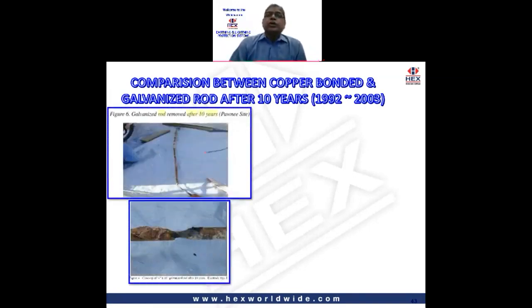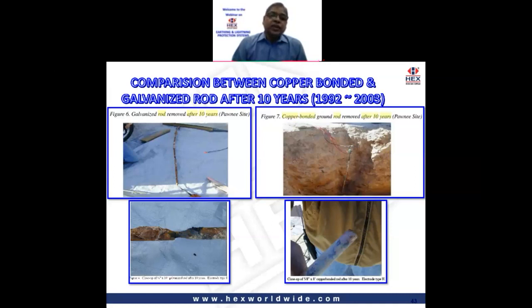So let us see, many people ask us this question: which surface treatment is better? Is galvanizing better or is copper plating better? Well, these are actual photos of earth rods from a study conducted by the NEGRP, the National Electrical Grounding Research Project in the US. They conducted it for 10 years. The objective was to compare the long-term performance of different types of electrodes. They buried different types of electrodes in different types of soils, and it was clearly seen that the copper bonded rods lasted longer than the galvanized rod. You can see the corrosion on the galvanized rod after 10 years, whereas the copper bonded rod is nearly intact.